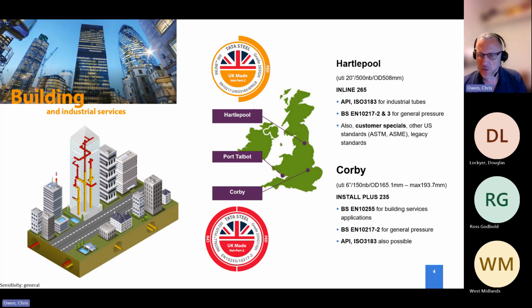That was basically to satisfy the old BS 1387, the gasless stroke building services product standard. Over the years we've had that standard replaced with BSEN 10255, but again it only goes up to 6-inch. With larger diameter pipework being pulled in, we're pulling in the industrial specs, still referred to as API, a legacy specification. This comes about because many decades ago, when larger diameter pipework was wanted, API, American Petroleum Institute pipework, was readily available in the UK market. It was here because of the North Sea and the American investment in that North Sea. So we tend to see people still talking about old legacy terms: medium weight, heavy weight, red band, blue band, sched 20, sched 40. It's a bit of a mixed match of different terminologies which are used.